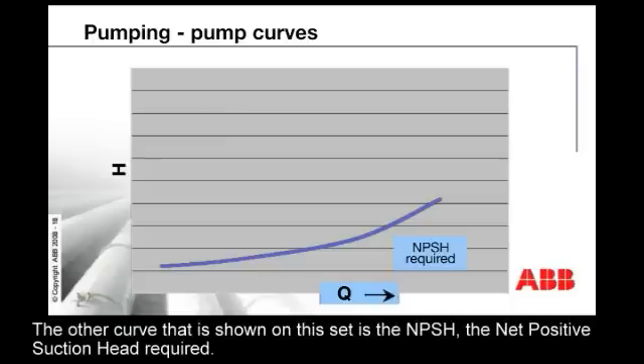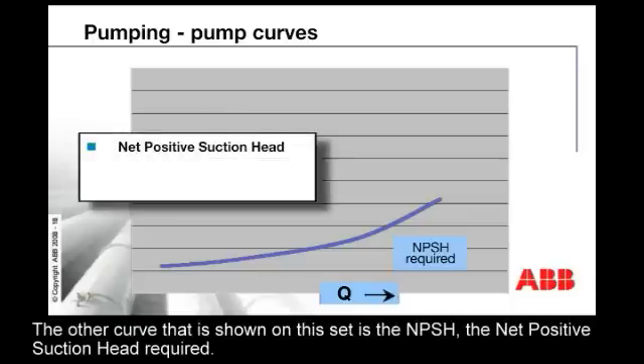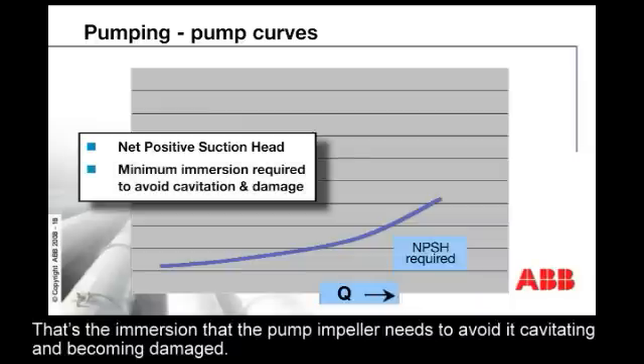The other curve that's shown on this set is the NPSH, the net positive suction head required. That's the immersion that the pump impeller needs to avoid it cavitating and becoming damaged.